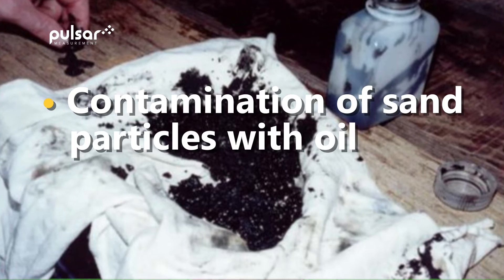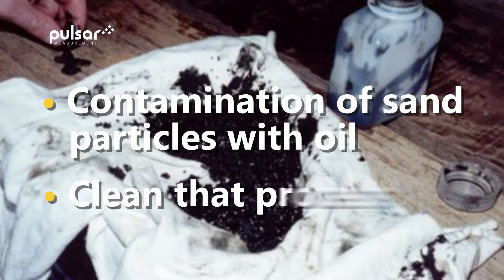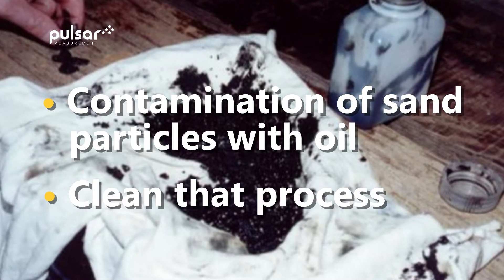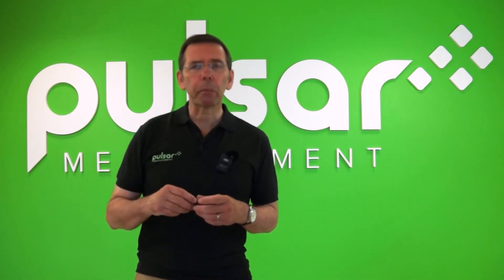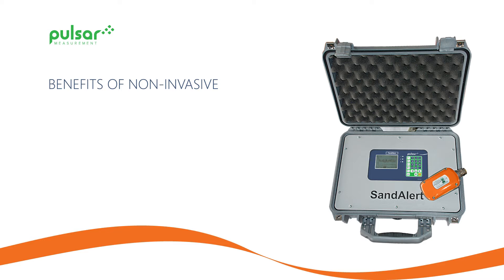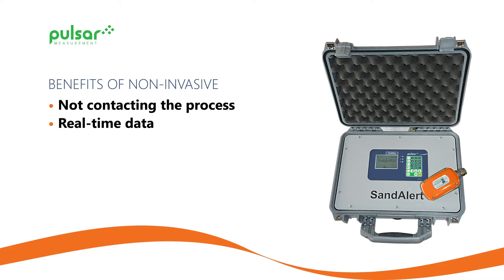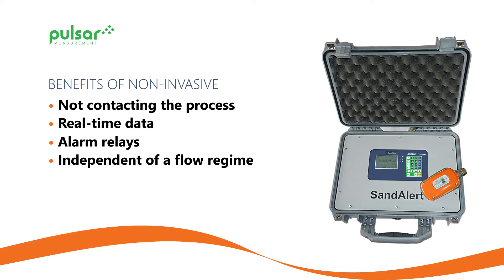Also, the contamination of sand particles with oil means the operator has to clean that process and then deal with landfill as well. There are different types of techniques to monitor sand — invasive and non-invasive. Using non-invasive gives the benefit of not contacting the process, so it's not sacrificial. Electrical resistance probes can be installed in the pipe, but they require downtime to install and don't give real-time data. The non-invasive sand alert detection system gives real-time data and alarms, and is also independent of flow regime.